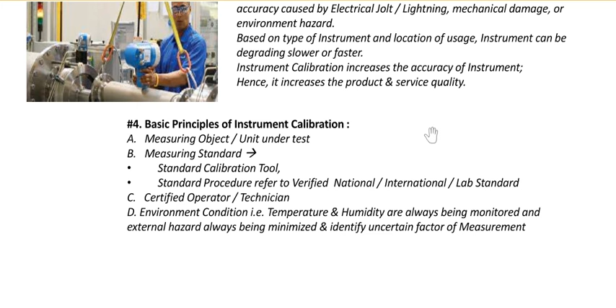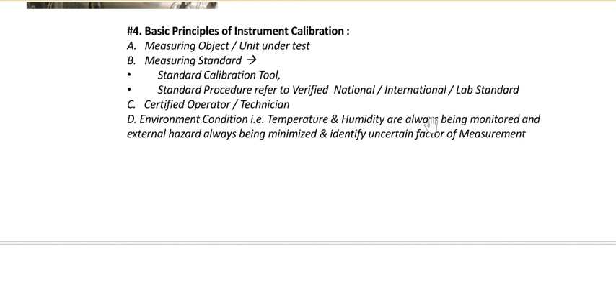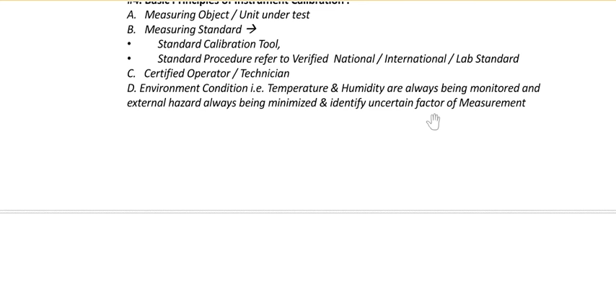Basic principles of instrument calibration. First is measuring object or unit under test, the flow meter that we want to calibrate. Second is the measuring standard, the standard calibration tool like Fluke and so on. Standard procedure refer to verified national or international or lab standard with the margin error of how much percent.